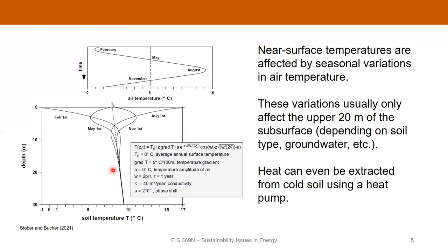This is actually a nice phenomenon: during winter the subsurface is warmer, so you can use that heat to heat your house. In summer, the subsurface is cooler, so you can use it as a heat sink. Most applications of these shallow geothermal systems have been in northern latitudes like Europe, mainly concerned with heating. But in places like Texas there's also an opportunity to use this for cooling in summer. Even when the subsurface temperature is only around 10°C, you can still extract that heat using a heat pump.